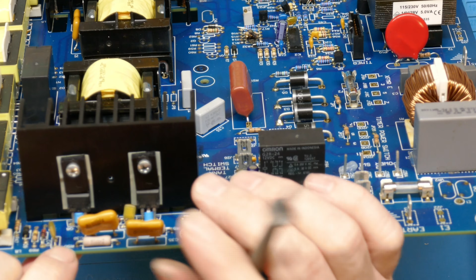So we have 4 IGBTs that are the high current output, and probably high frequency output, for our ultrasonic transducers. I don't have the meter on the screen, but they're showing shorted. In case you can't see this, I'll give you a close-up here in the top right. I definitely see where these have let the magic smoke out.